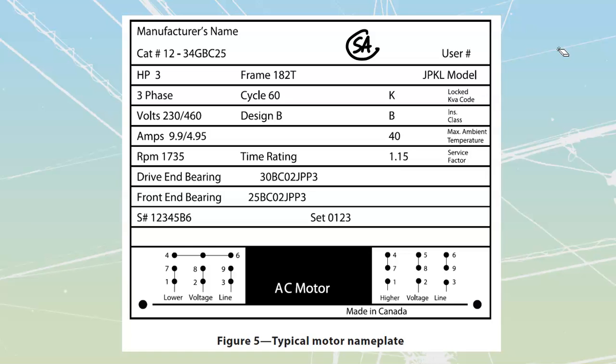So we'll start with our nameplate over here, nameplate information. This is going to be typical stuff. Now, for us to have a certified motor under the Canadian Electrical Code, and particularly here in British Columbia, it has to pass some approvals. One of those sets of approvals is that they want to know the manufacturer's name and the catalog number. They need to have some trackability. It's part of the process of certification, saying who built this and where am I going to find the information, or what's the name that I'm going to use to look up the information in case there is some sort of fault. The whole idea is that we're going to have ready information available for us.